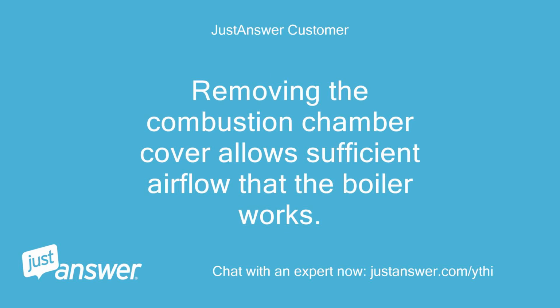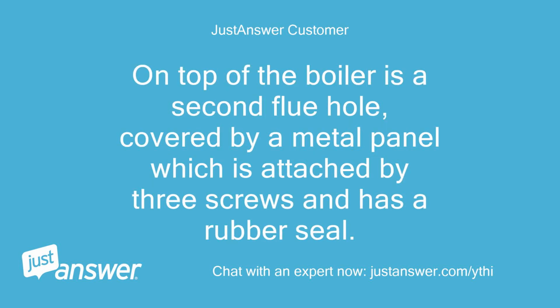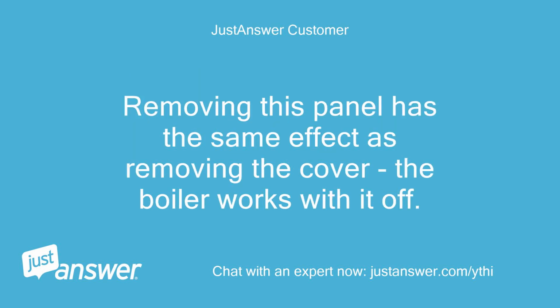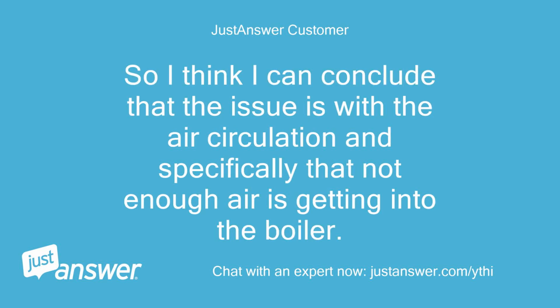Removing the combustion chamber cover allows sufficient airflow that the boiler works. On top of the boiler is a second flue hole, covered by a metal panel which is attached by 3 screws and has a rubber seal. Removing this panel has the same effect as removing the cover, the boiler works with it off. So I think I can conclude that the issue is with the air circulation and specifically that not enough air is getting into the boiler.